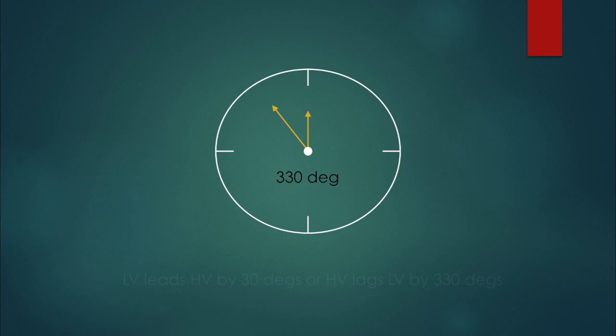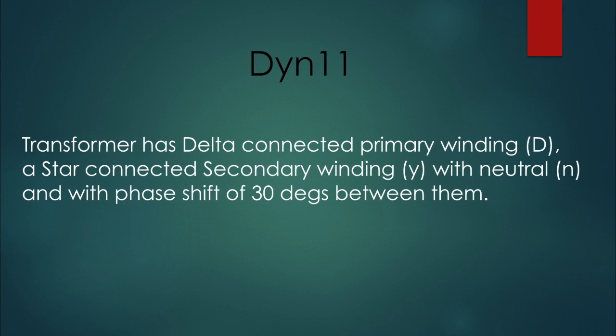We can say that LV winding leads the HV winding by 30 degrees or high voltage winding lags the low voltage winding by 330 degrees. So that is why 11 represents 30 degrees. So DYN11 indicates transformer has delta connected primary, star connected secondary winding with neutral and with phase shift of 30 degrees between them.